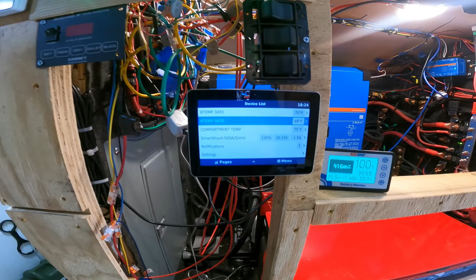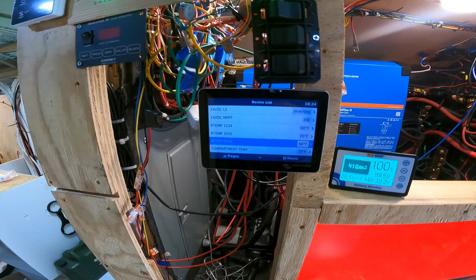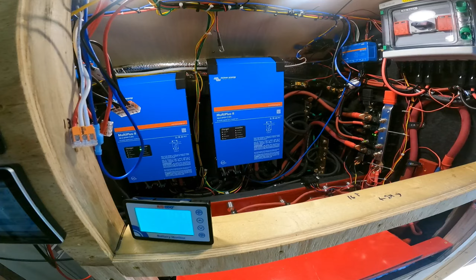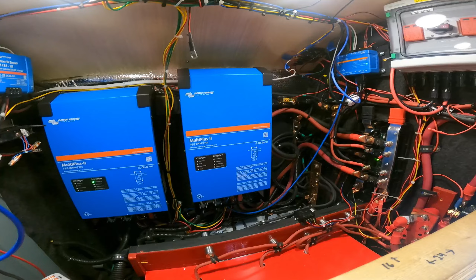After I got all of that squared away, got all my lessons learned, got all my COM ports connected and corrected and all those kind of things, everything came up as it was supposed to. Just lesson learned, ignorance of the equipment, ignorance of the communication protocols. Took me a bit to figure it out, got it all figured out, and now it's all working. So everything on the 24 volt side is up and running and has power. My second inverter is off because it's not configured for split phase, and if I do, it gives me a crap ton of errors that I just don't want to deal with. And it's because it's not configured.